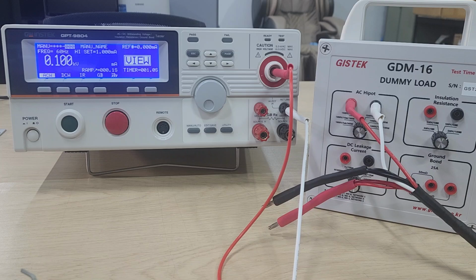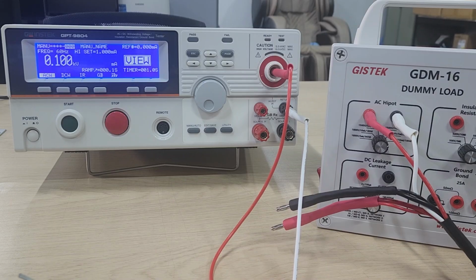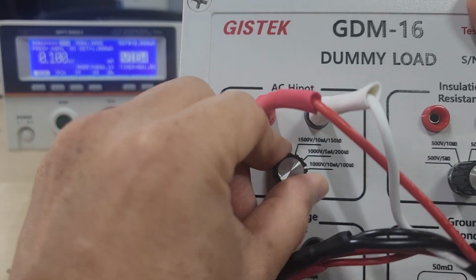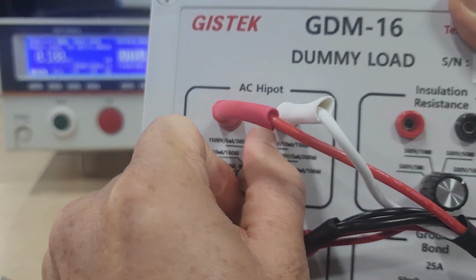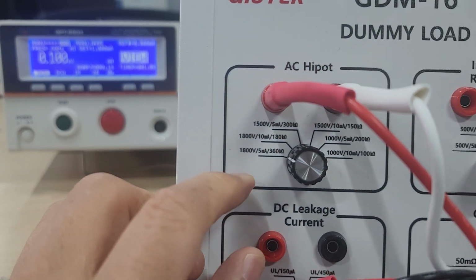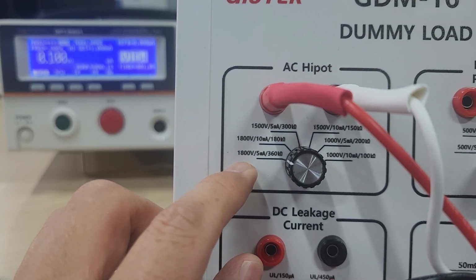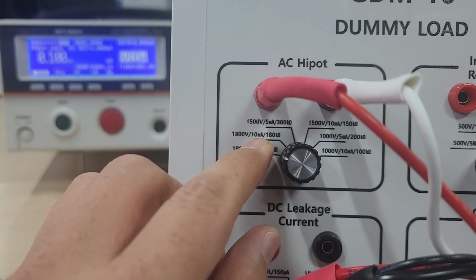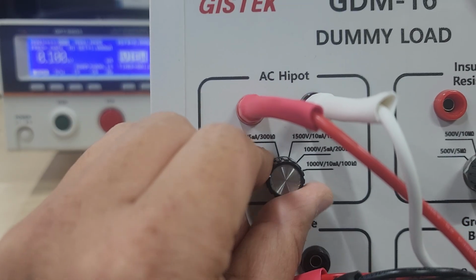And number 2, select the withstanding voltage test channel from the dummy load. For example, turn the knob to select the 1800 volt and 10 milliampere channel.